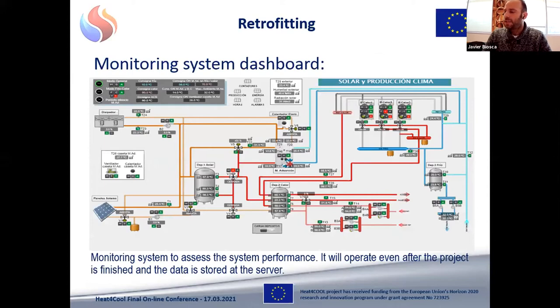Here we can see a facility scheme from a screen of the monitoring system dashboard. You can see we have the solar thermal panels connected to the solar storage tank, which feeds the absorption unit. And this absorption unit needs to be connected to a recooler in order to dissipate the waste heat. And this generation system is supported by the old heat pumps in order to charge the cooling tank and the heating tank.